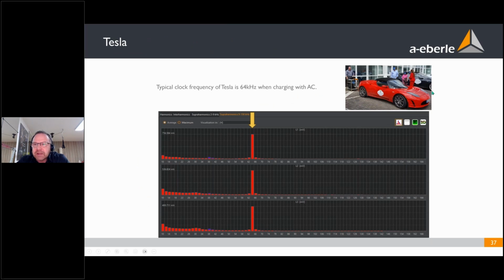So here is a nice Tesla, and for Tesla, the interference is typically the same for new Teslas. If you measure a Tesla, it is producing interference to the network at 64 kilohertz. This is typical for Tesla. 64 kilohertz is a high frequency, and most of the analyzers will never detect this frequency.